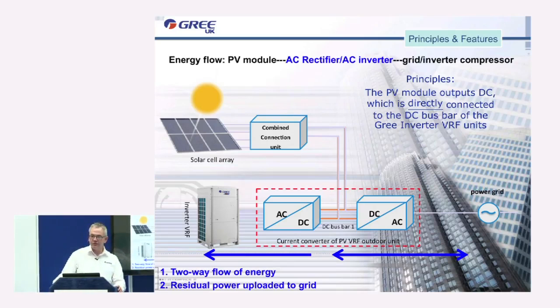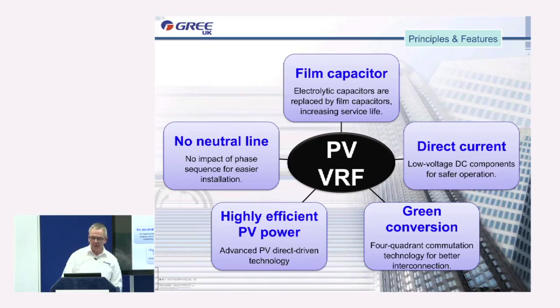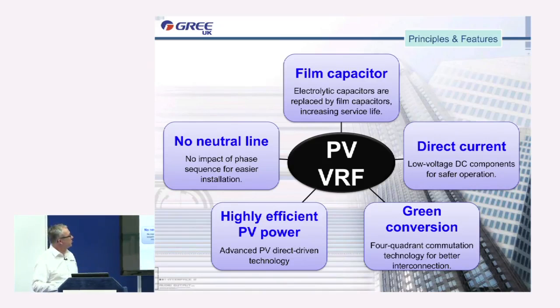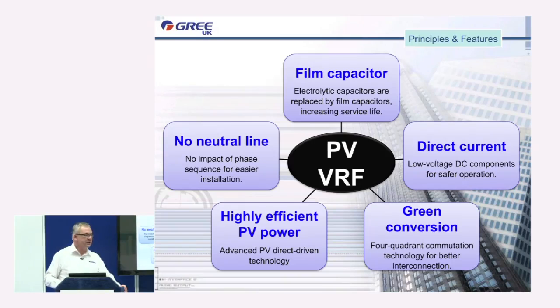The basic principle of the system is to use PV energy directly connected to the DC bus bar within the unit. The main features of this system from Gree are two-way energy flow and residual power that can be fed into the grid. Additional features are some of the components within the inverter unit, the VRF unit, which allow us to control and manage the use of the generated energy.